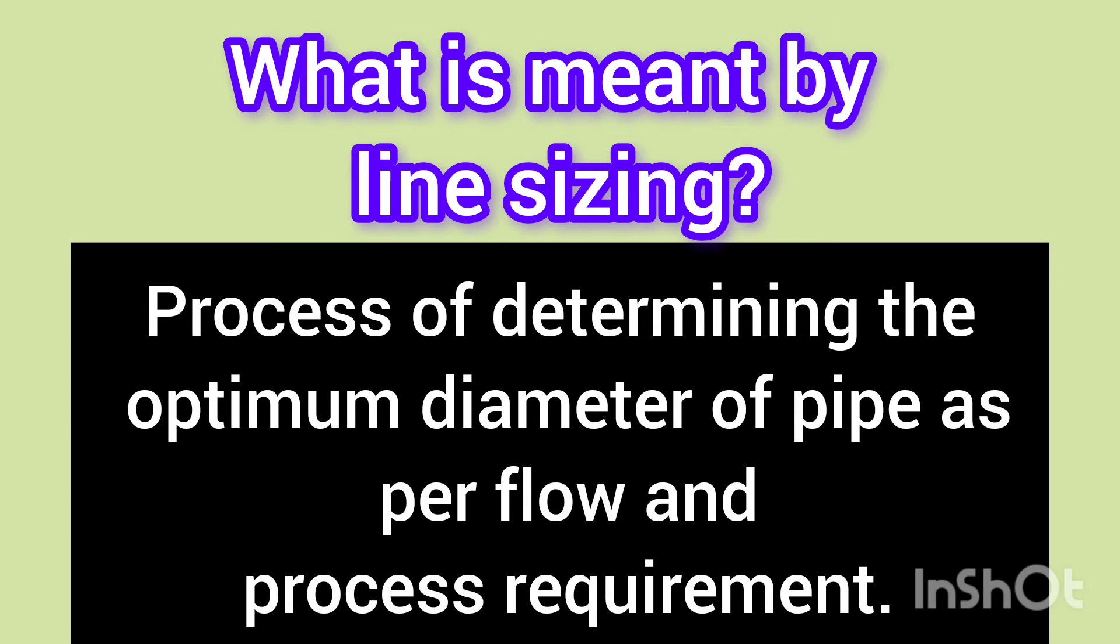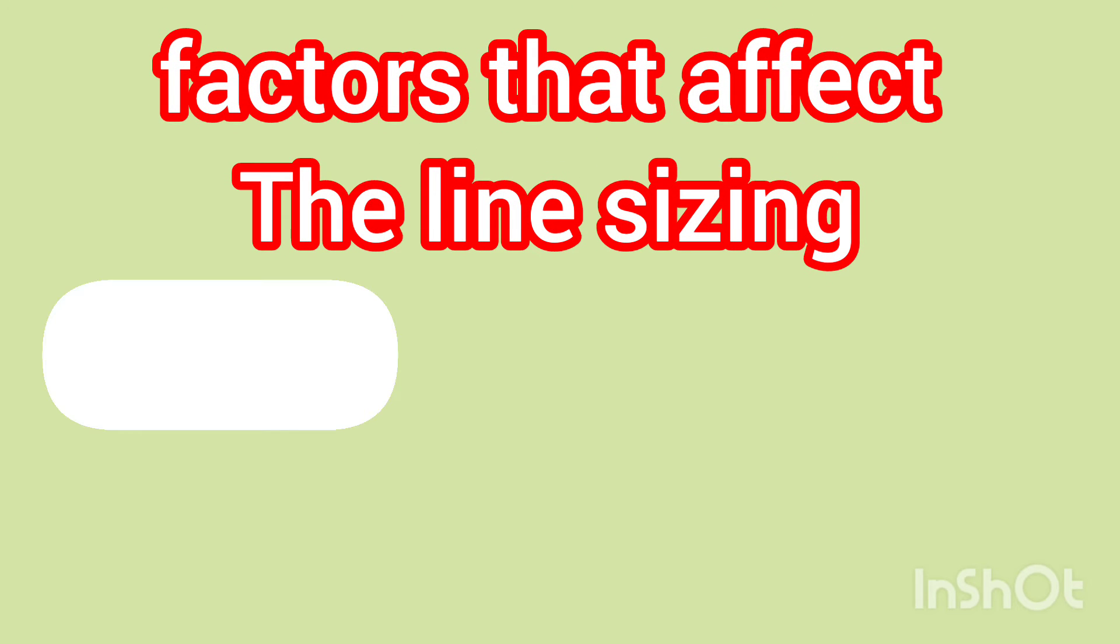Now let's discuss the importance of line sizing. The importance becomes evident when we consider factors like erosion velocity, costing, and pressure drop. Erosion velocity is a critical consideration - if the fluid velocity in a pipe is too high, it can lead to erosion and damage over time. Line sizing helps us avoid this issue.